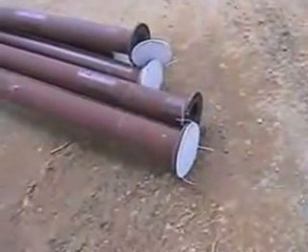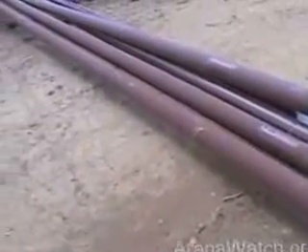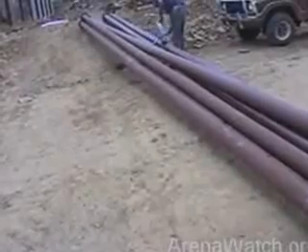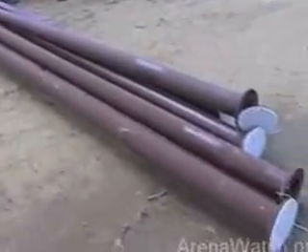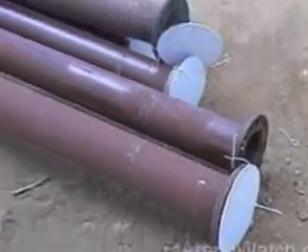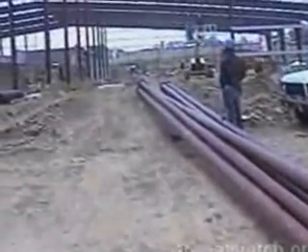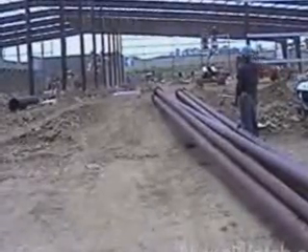These are the transmission lines for connection from the mechanical room floor and distribution of the secondary coolant fluid from where the mechanical room is actually into where it's distributed on the manifold on the rink floor. As you can see, they're all prefabricated and equipped with flanges, so the connection in the field is relatively easy. These are primed and will be fully insulated after they're put into place.